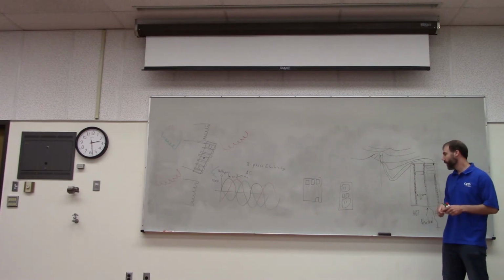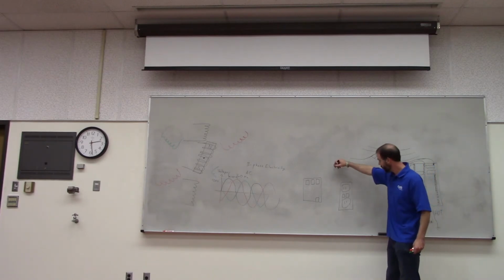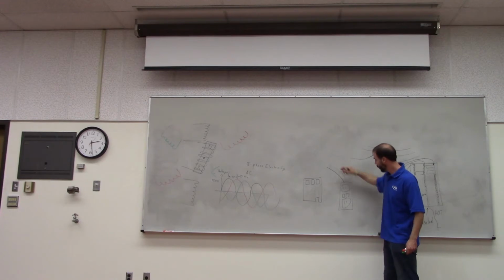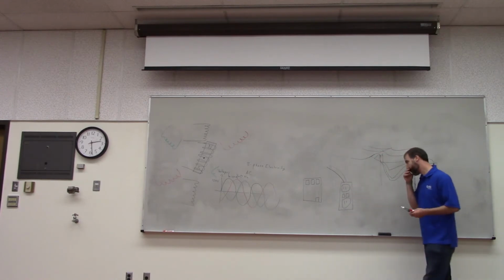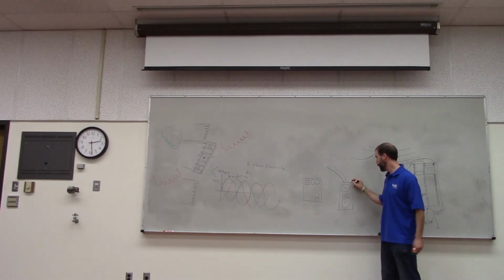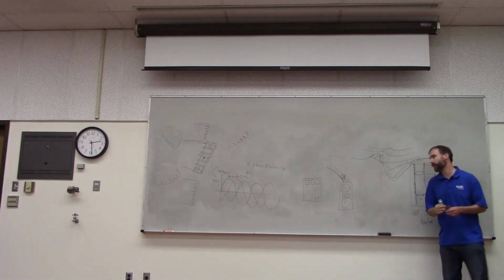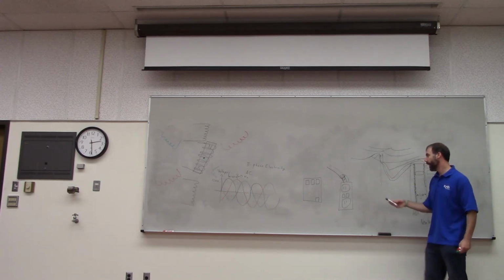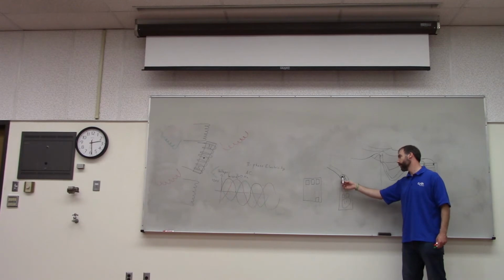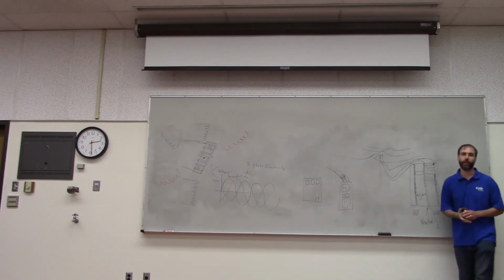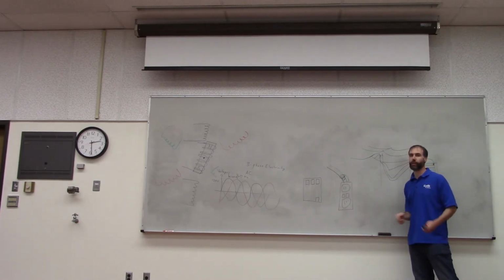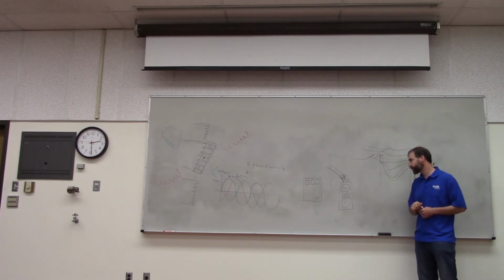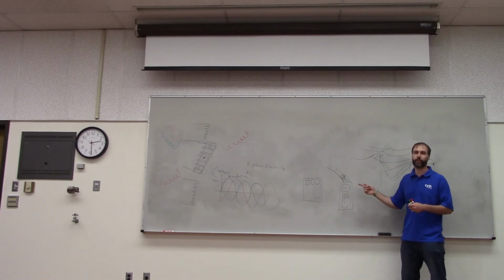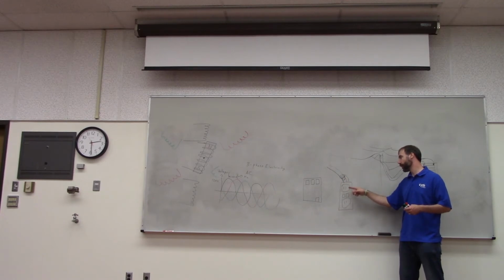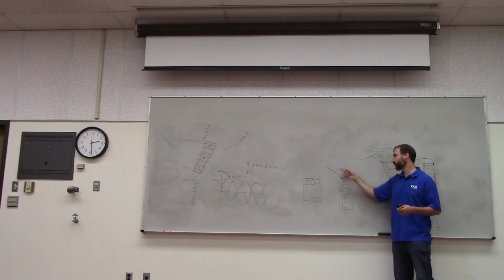So basically, the way that these work is that you have the electric wires coming in. One side of the outlet is hot and the other side is neutral. And there's a little sensor inside of this box that goes around these wires and measures the current going in and coming out of the outlet through these wires. And this sensor is always checking to make sure that the same amount of current that's coming in is going out again. Okay? If the amount of current going in matches the amount of current coming out, then the outlet knows that everything is working correctly, right? The current is going in through the hot wire, it's going through your appliance, and then it's going back out through the neutral wire.